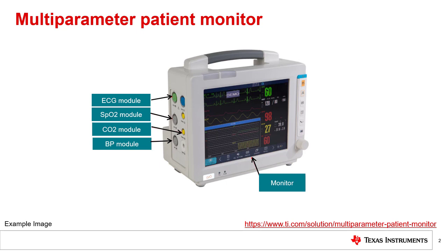By definition, a multi-parameter patient monitor measures multiple parameters like electrocardiogram or ECG, blood oxygen concentration or SpO2, temperature, blood pressure, carbon dioxide or CO2, and multiple other gases. These parameters are typically measured by using isolated modules which can be connected to the main unit, called monitor.